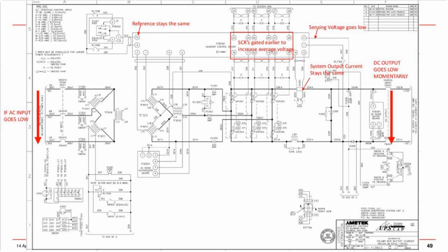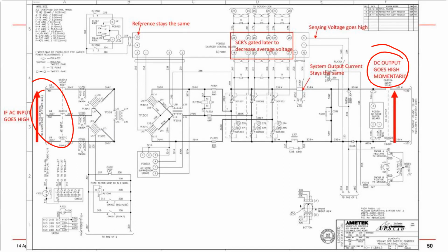So remember, if our input goes down, the DC goes down momentarily, and the SCRs have to be gated earlier to increase the average voltage until this point goes back to 135 volts. And if the AC goes high, the output goes high momentarily until the feedback circuit takes over and the SCRs are gated later in their cycle, which will decrease the average voltage.